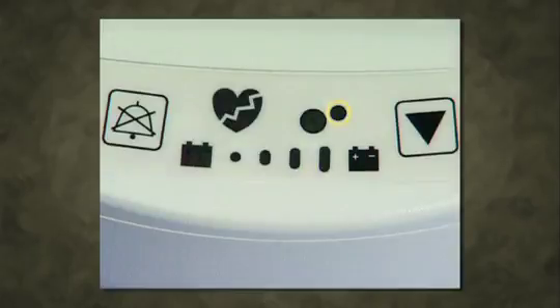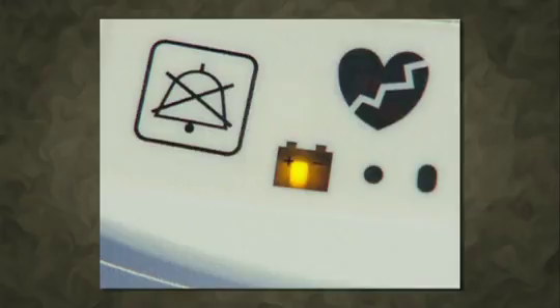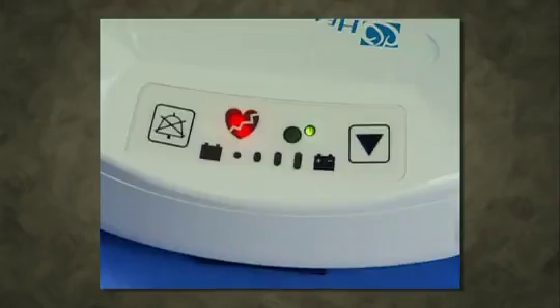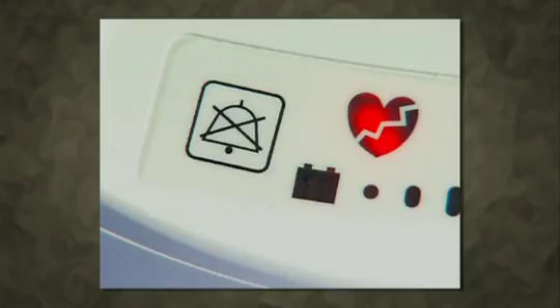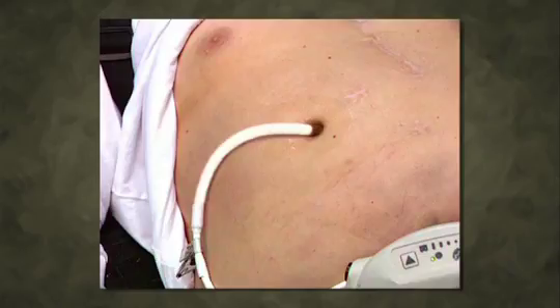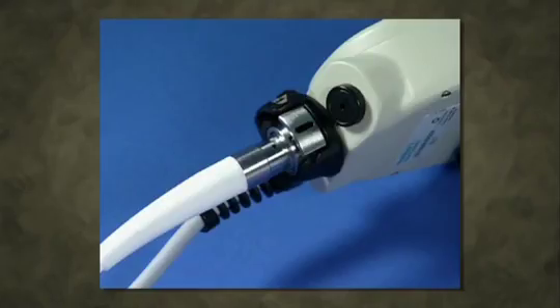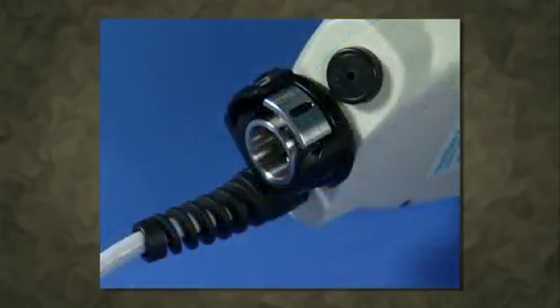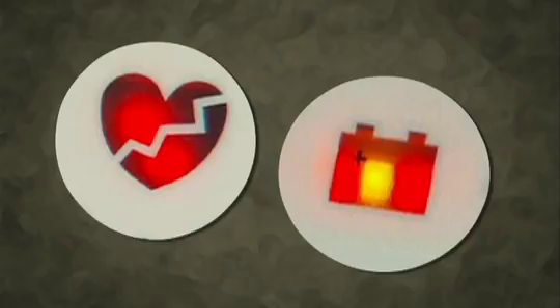And while you don't need to know the meanings behind all the warning lights and sounds, you should be aware of the red heart alarm. This is indicated by the broken heart symbol illuminating red on the controller along with a steady audio tone. This alarm could indicate that the percutaneous lead coming from a patient's abdomen has become disconnected from the system controller and is therefore not powering the LVAD. It may also indicate that the battery power is extremely low and in danger of running out imminently.